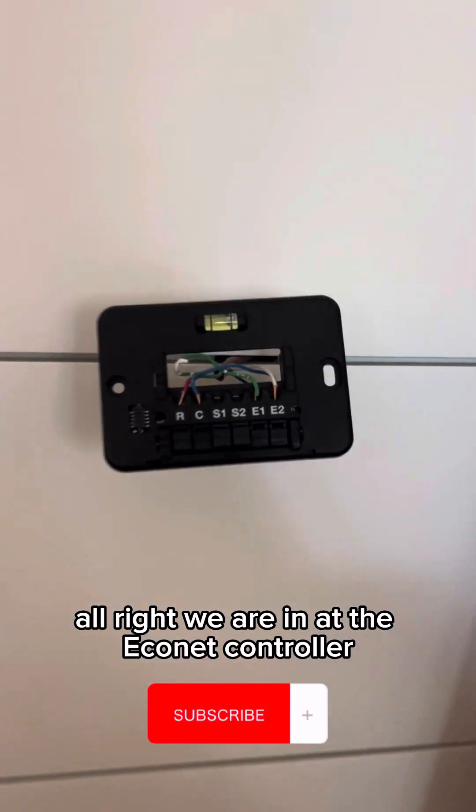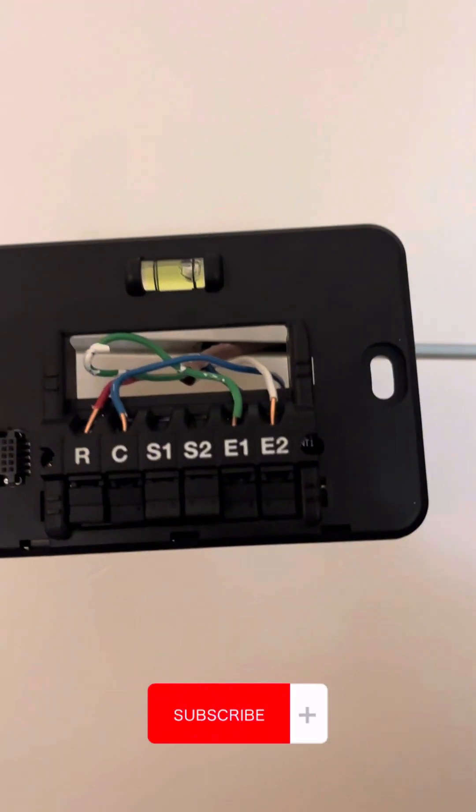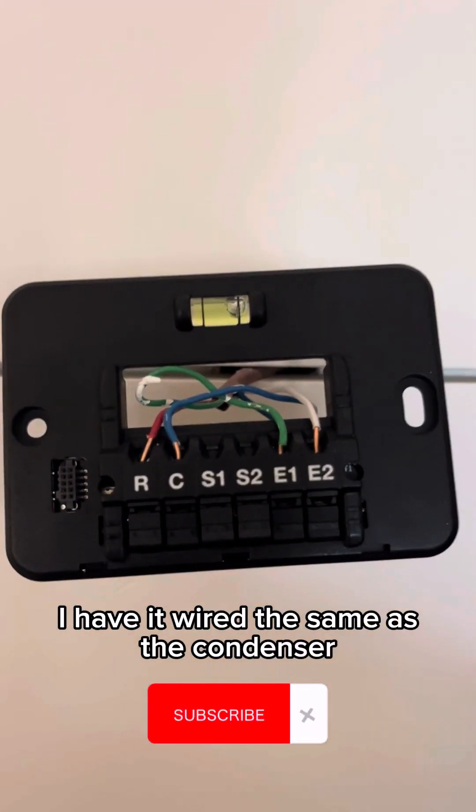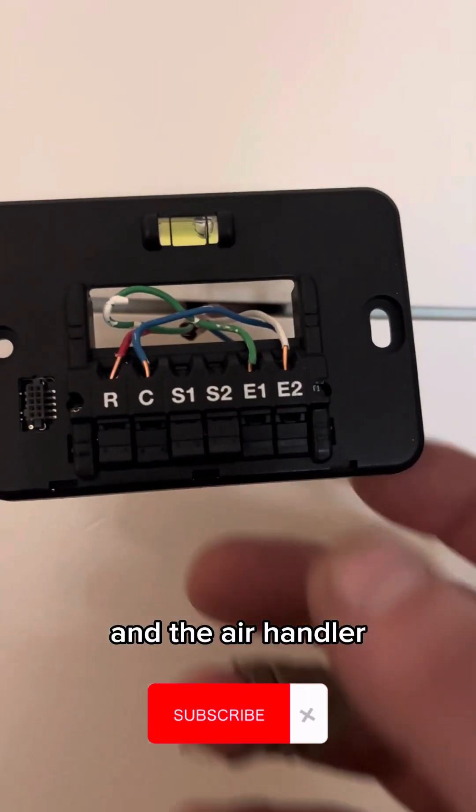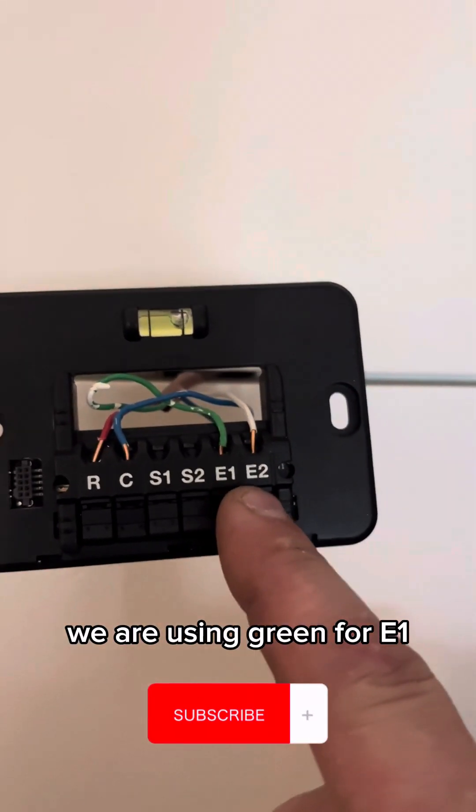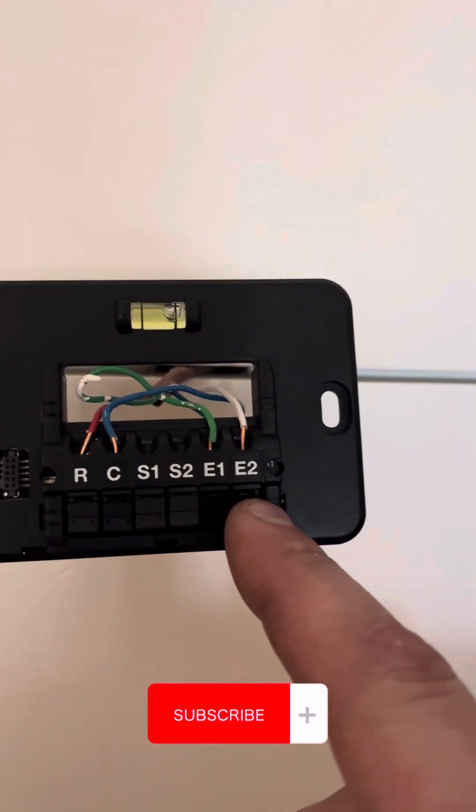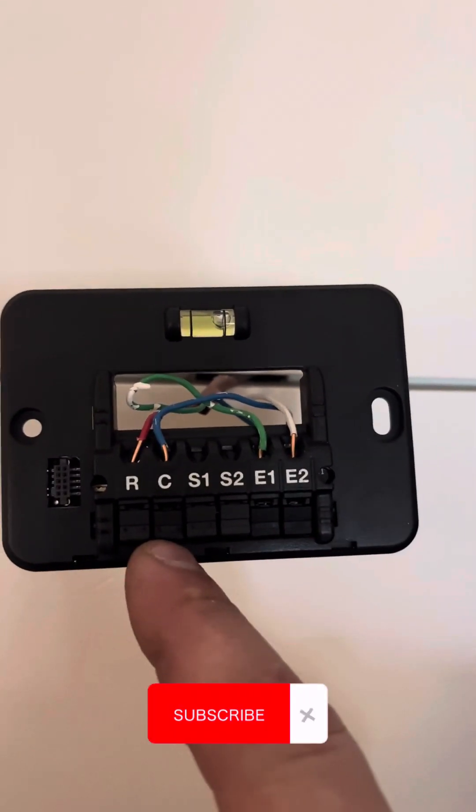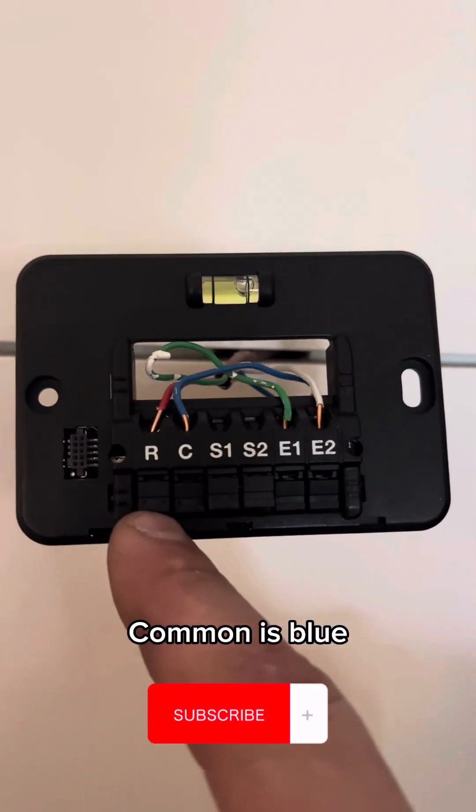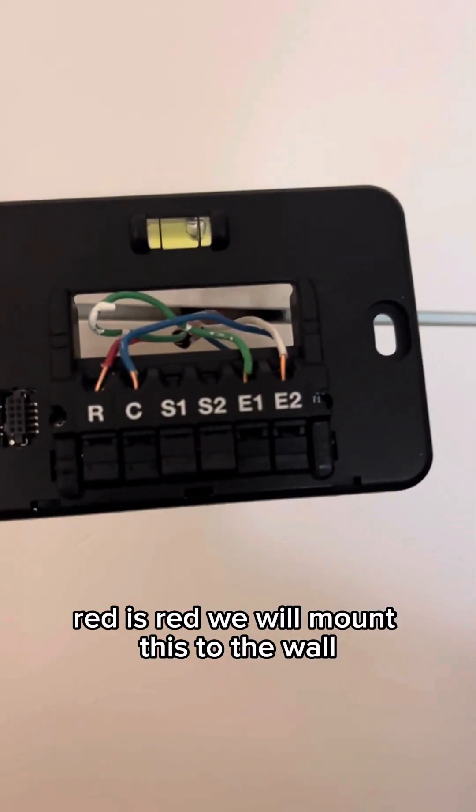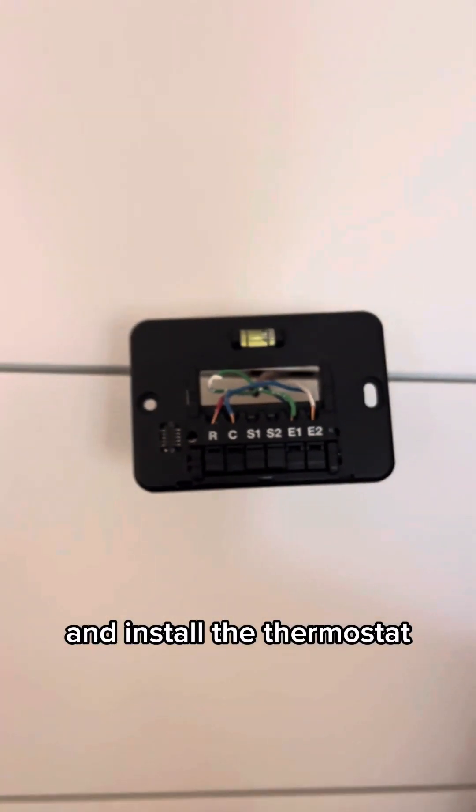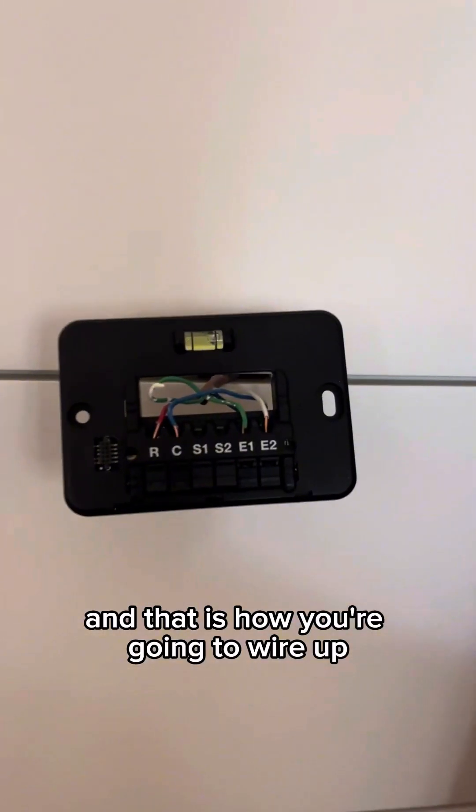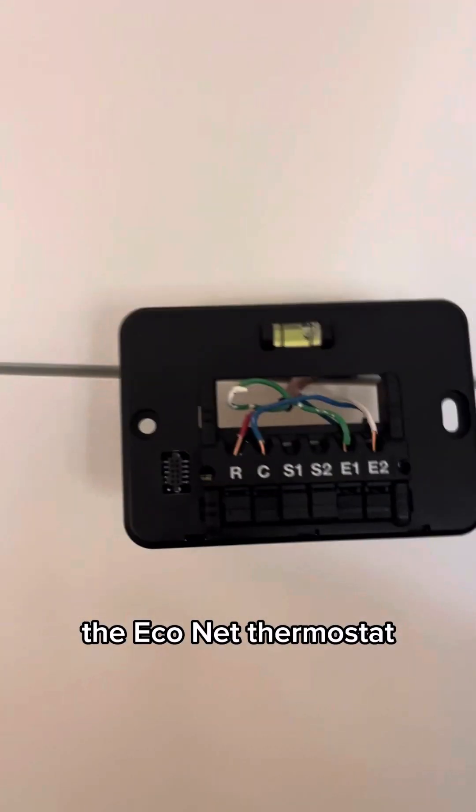All right, we are in at the Econet controller and I have it wired the same as the condenser and the air handler. We are using green for E1, white for E2, common is blue, red is red. We will mount this to the wall and install the thermostat. And that is how you're going to wire up the Econet thermostat.